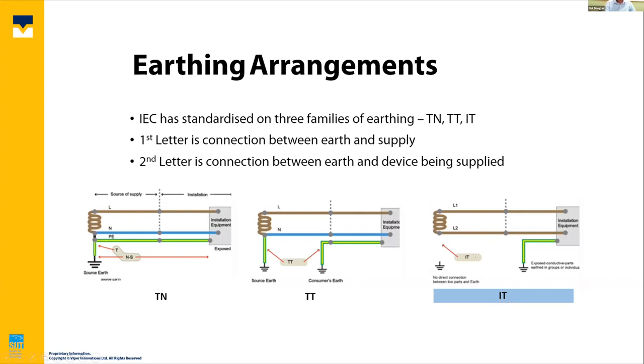If you have an IT system, an individual can come along and grab hold of conductor L1 or L2, and all they would be doing is referencing that conductor to Earth. There would be no current flowing through them. It would be perfectly safe to do so. So you can see that an IT system is generally much safer for users, for individuals.